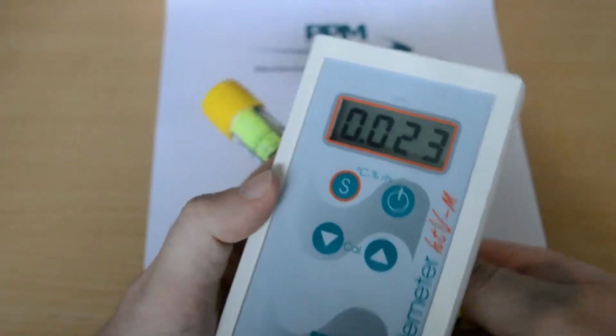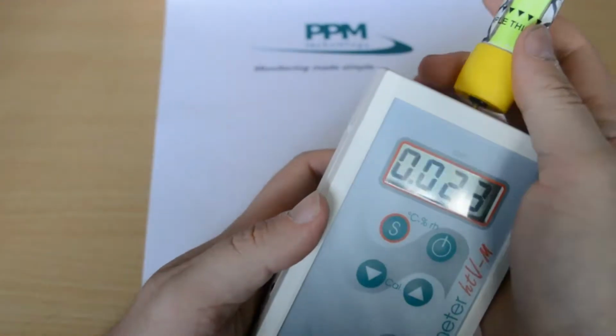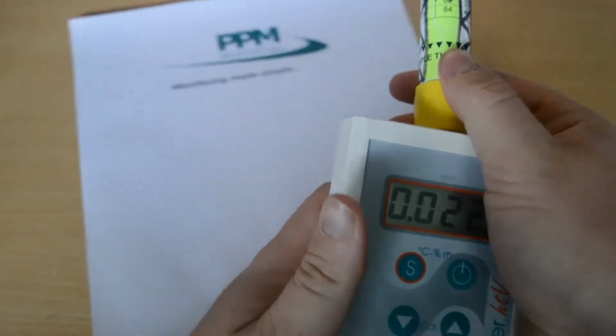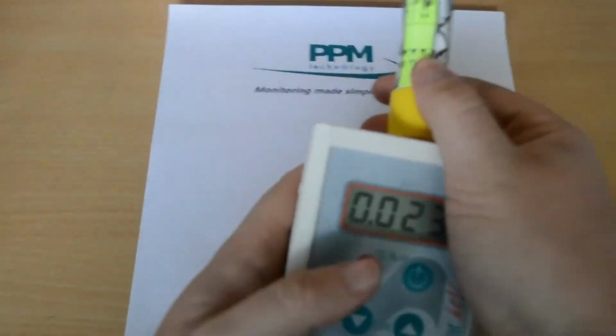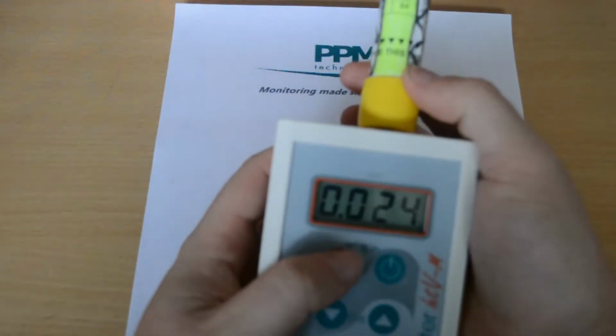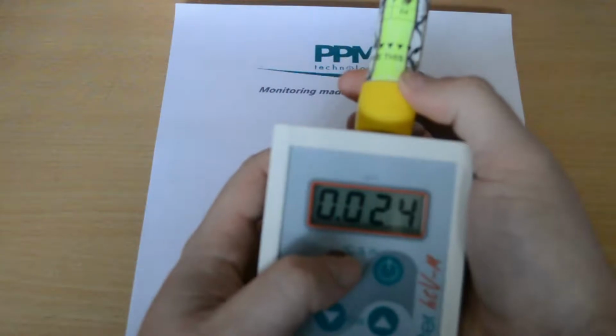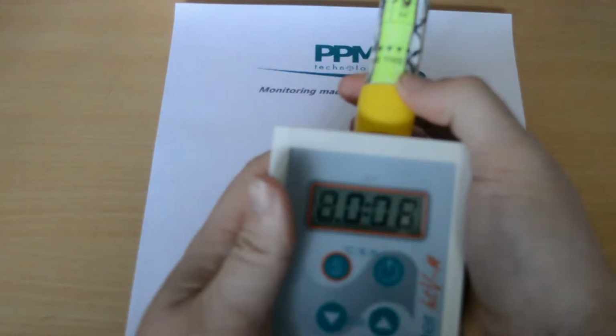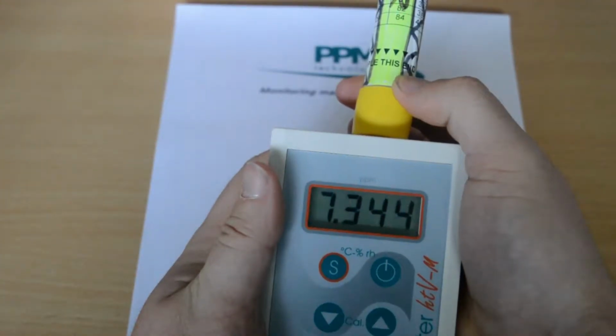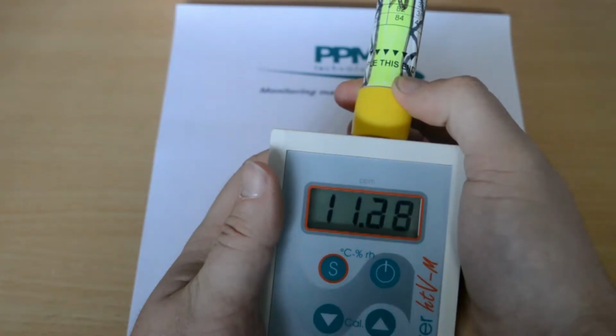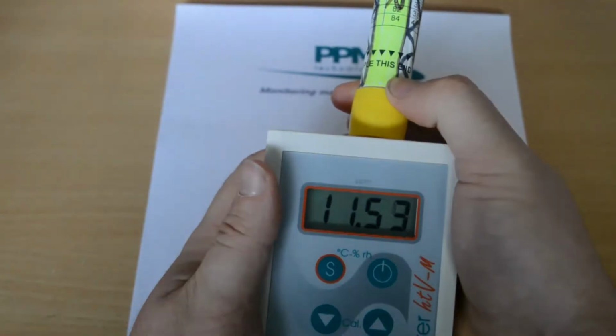If the initial value or the rate of change was in excess of 0.3, then it is likely that your sensor has been damaged. Contact PPM Technology or your dealer for further details. Otherwise, continue with the instrument still in test mode. With the sample nozzle inserted into a valid calibration standard, press the S button to take a sample.